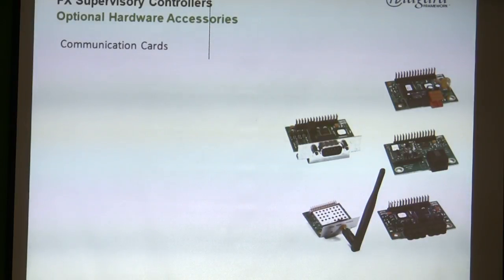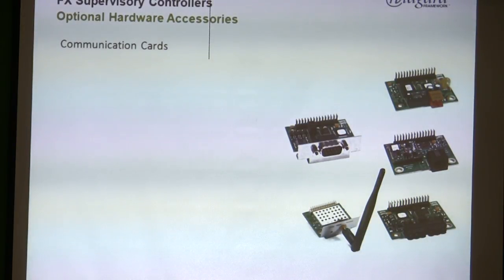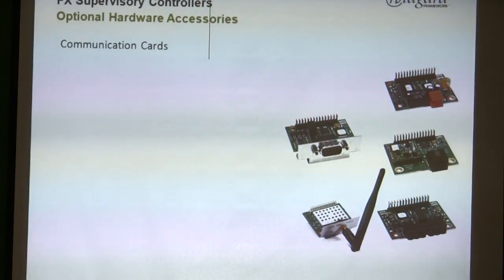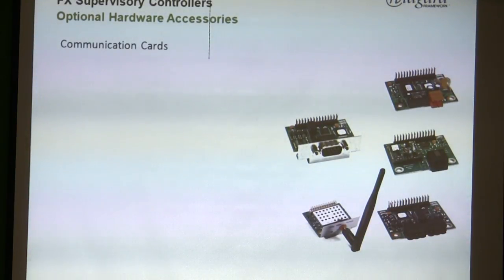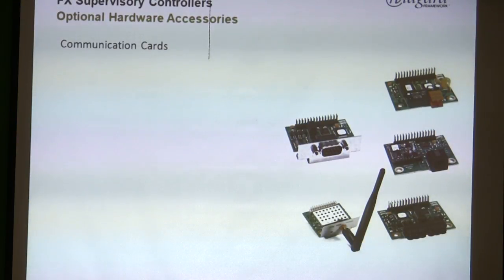If you have a really big job with tons of network activity, you need an FX-70. If you're doing a small job — a couple VAV boxes and a rooftop unit — you can get by with an FX-20. It's all based on how much you're pulling into that system. You might have an FX-60 with just one air handler that's too much for an FX-20 because you have tons of stuff to pull in.